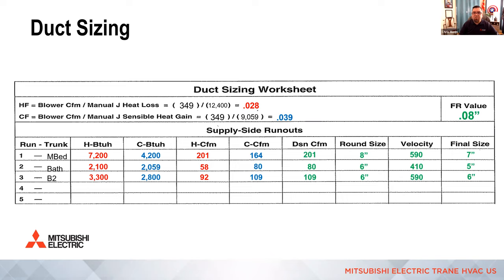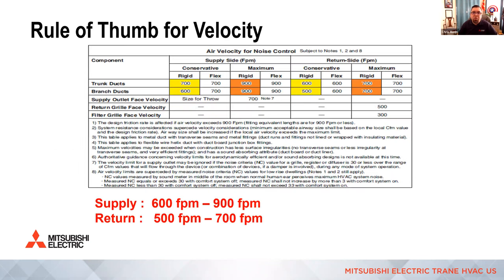So Lee asked about face velocity. So that must be on the previous screen. Hold on one second. So face velocity is going to be at the register. So typically you size your outlet registers. This is actually Manual T. When you select registers, your maximum face velocity should be 700 feet per minute on the supply. That gives you, typically on the correctly sized register, a 0.03 pressure drop, and anything less than that won't be noisy. So it's the measurement of the air at the register, at the face, and the same thing at a filter grill face velocity. Now, to Steve's point, I have gotten away with sizing filter grills based on face velocity almost across the board. It's really easy to do that because the pressure loss is very little in a return. There's no dampers. You just have that one register.